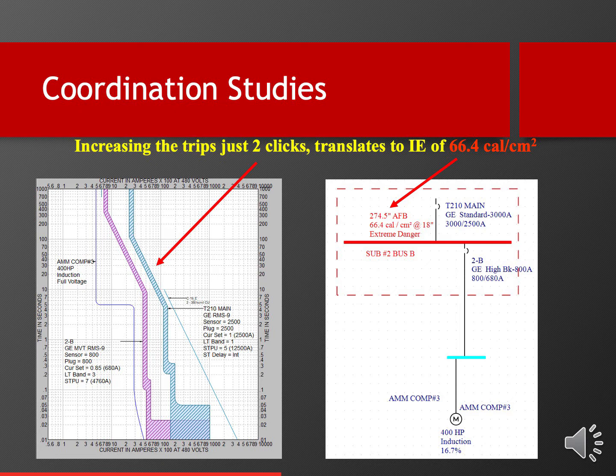There is a label on sub 2 bus B that says 2.9 calories to this day. And that is true, providing that nobody changed those settings. So this is probably the accident of the future, where somebody may change the settings on a device and they are actually not thinking about what it might do to the incident energy there, and it could produce a death trap for somebody else.